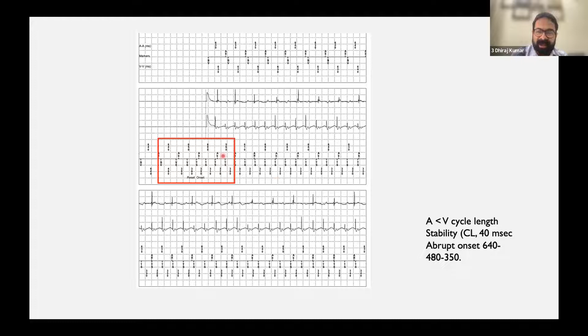The device then starts giving ATP. So this is the burst ATP at a constant cycle length. It gives two burst ATPs. If you remember the device programming, we had two burst ATPs and then two ramp ATPs. And just after the ramp ATP, the tachycardia accelerates. So it doesn't give the second ramp ATP, it goes into the VF zone, and therefore the device delivers shock.